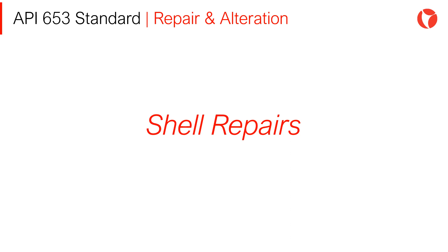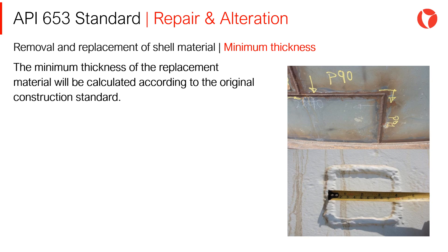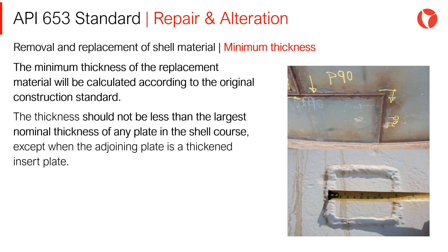Let's review shell repairs in detail. Removal and replacement of shell material — minimum thickness. The minimum thickness of the replacement material will be calculated according to the original construction standard, normally the API 650 standard. The thickness should not be less than the largest nominal thickness of any plate in the shell course, except when the adjoining plate is a thickened insert plate.